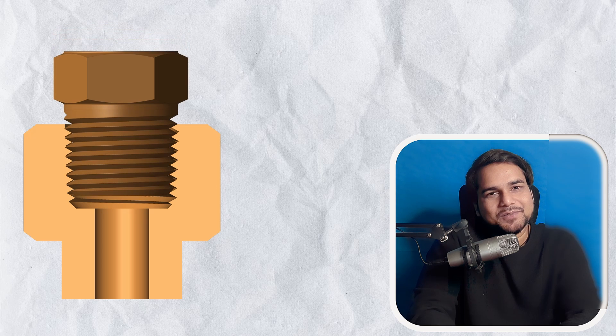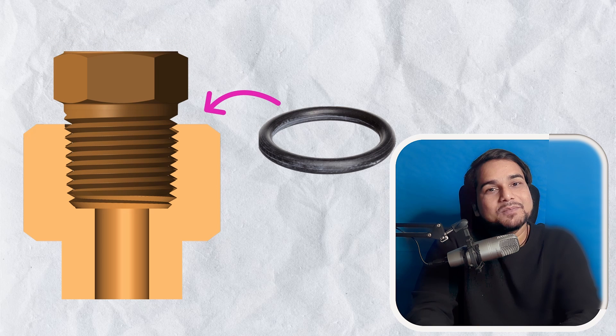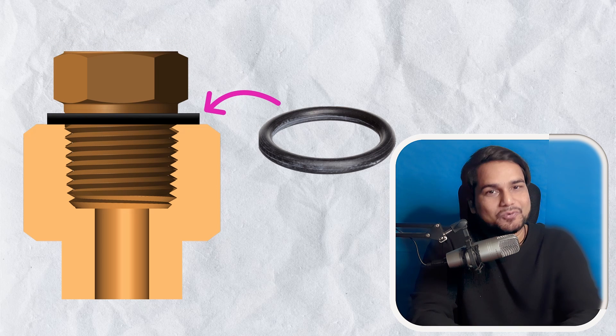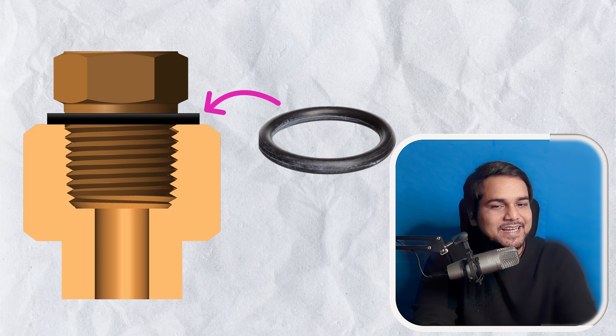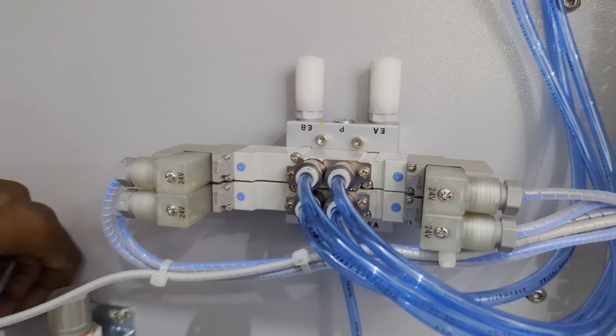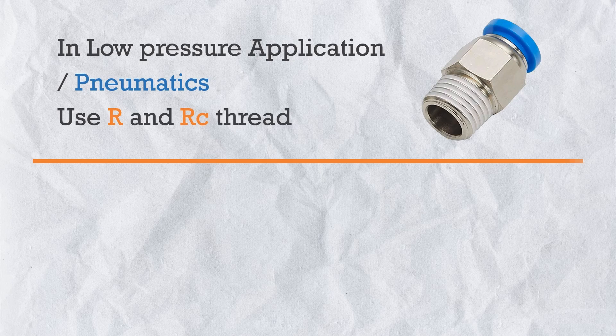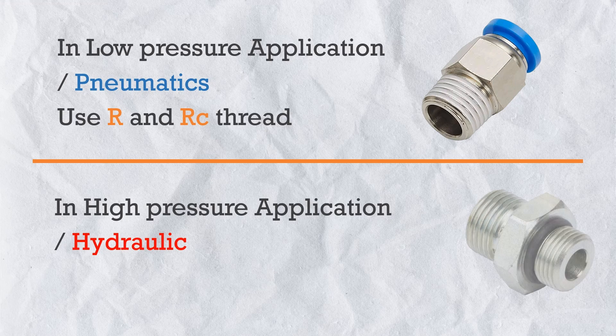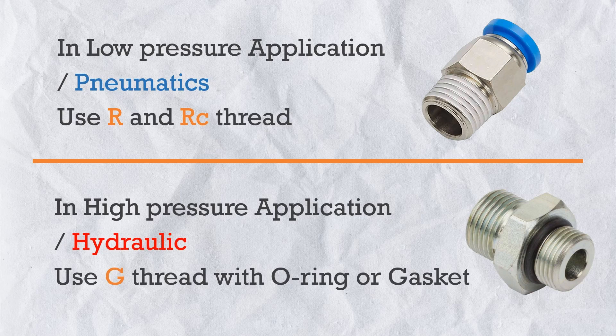Just for curiosity — can we use taper thread with an O-ring to further improve sealing? No. With taper threads, the connection face matching can be difficult, so always avoid using an O-ring with taper thread. In summary: for low-pressure applications like pneumatics or gases, use taper thread — R and RC thread. For high-pressure applications like hydraulics, always use G thread with an O-ring.